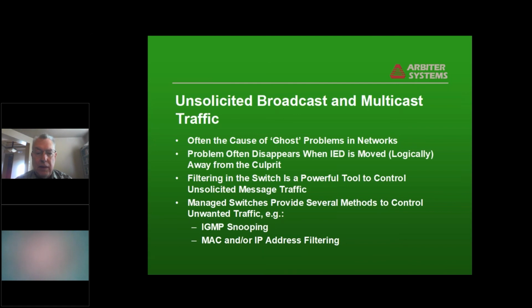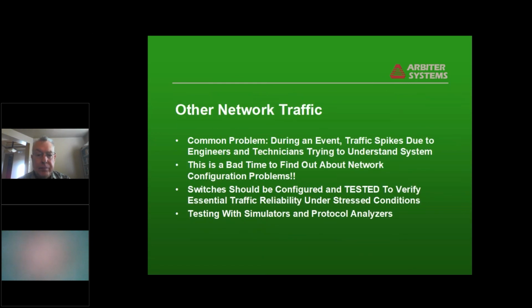One of the things we found in network time applications and other applications with synchrophasors is what we call ghost problems in networks: things that work fine and all of a sudden act strange, or every so often act strange. It's often caused by unsolicited traffic, and broadcast and multicast is often an offender, because there are situations when broadcast packets get sent out and overload IEDs that don't have the capability of handling a lot more data than they expect. Sometimes these problems disappear when you move the IED to a different location or put it on a different switch. When you have these kinds of problems, unsolicited broadcast traffic and background traffic that's not intended for that IED but is ending up there, you can turn on switch filtering to control that. IGMP snooping is one way, and MAC and IP address filtering is another.